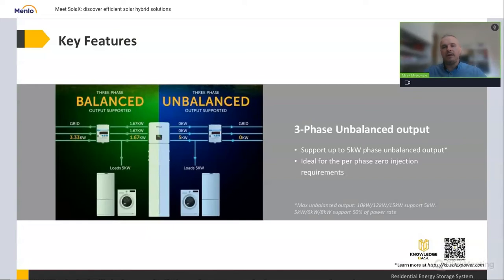So the limits are up to 5 kilowatts per phase, or up to 50% of the inverter output power. So if you have a 5K inverter, it will have only 2.5 kilowatts maximum per phase, because that's its 50%. But a 10K inverter will match both of those limits, so it will have 5K on the phase and also 50%, that is 5K on the phase. And it is really working. I saw this many times. It's really doing the work within those limits.